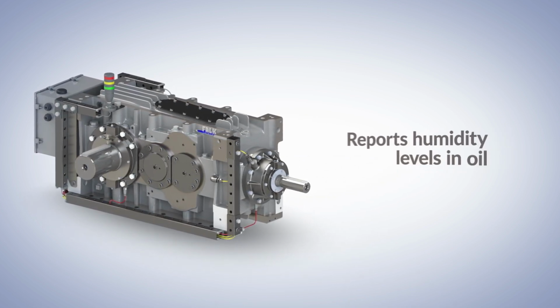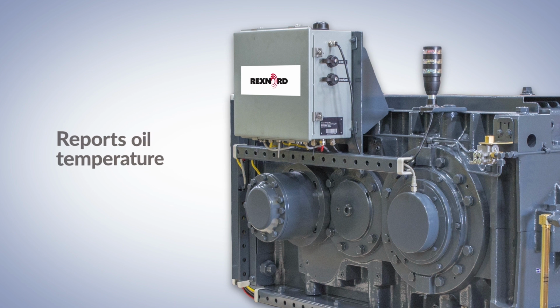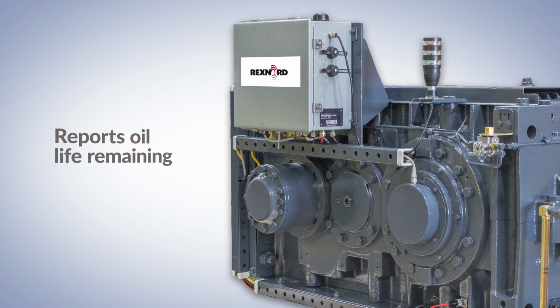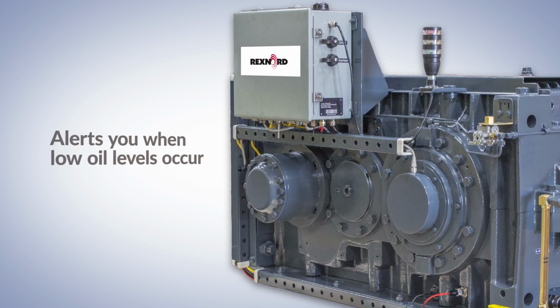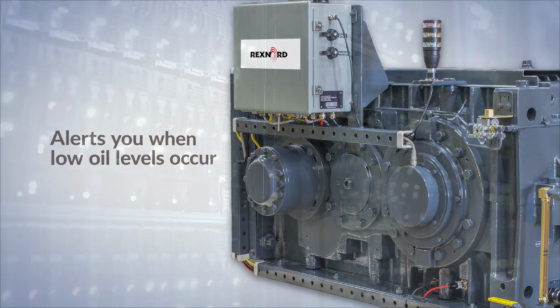Our smart monitoring system measures relative humidity within the oil to prevent contamination. It measures oil temperature to keep the cooling system working properly, preventing oil breakdown. It measures oil oxidation to ensure continued lubrication of components and predicts when an oil change is needed. It sends alerts when oil levels get low, preventing friction-induced failure.